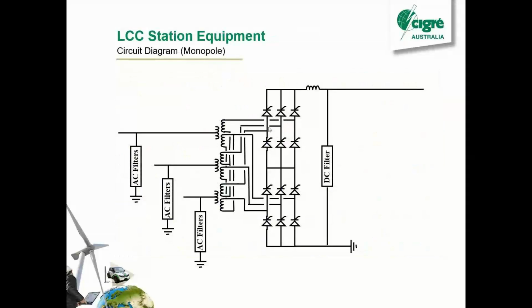Okay, now we'll look at some of the station equipment for LCC. So this is sort of the basic circuit diagram for a 12-pulse converter monopole. So for the New Zealand scheme, we've got 2 of these basically, but one's connected on the negative side. So on the AC side, you start with your AC filters. These AC filters will provide your megavars for the converter, but they'll also provide harmonic filtering to cancel out those harmonics. Then you've got your converter transformer.